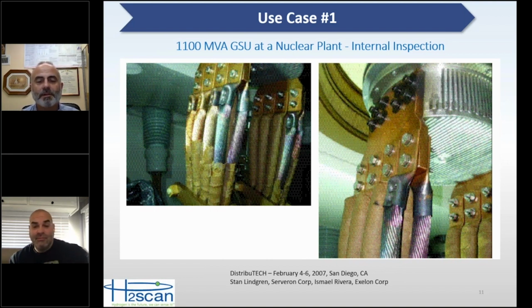What they found is that the leads closest to the winding, the leads closer in the near ground in the picture, were all overheated. They were carrying a lot more current than the leads farther away from the winding, and so there should have been a flux shield in between the winding and the low voltage leads, so that you didn't have that situation of some leads carrying a lot more current than the others.